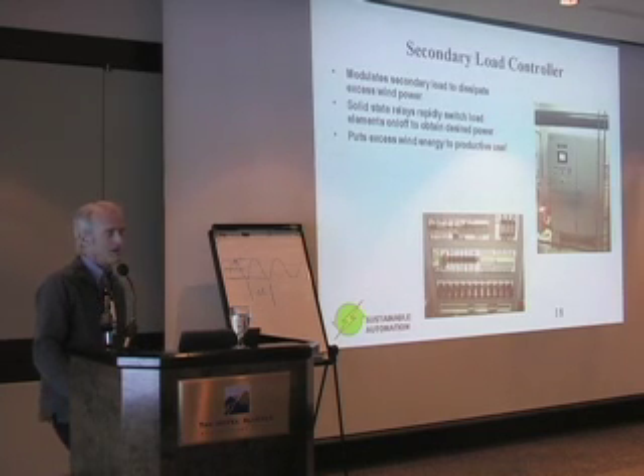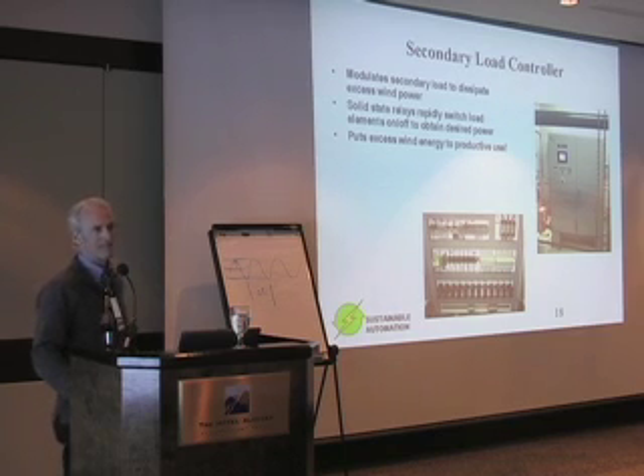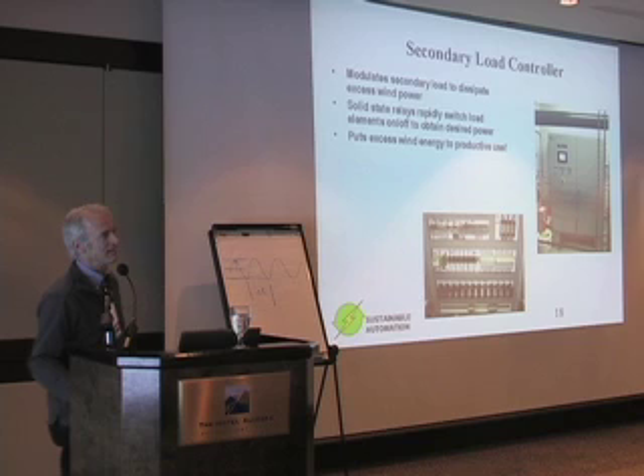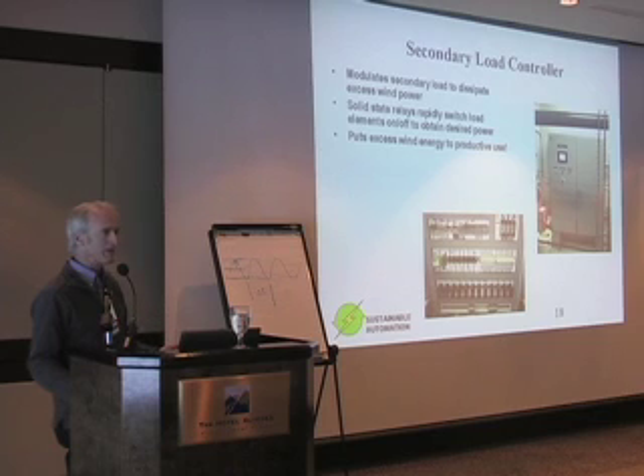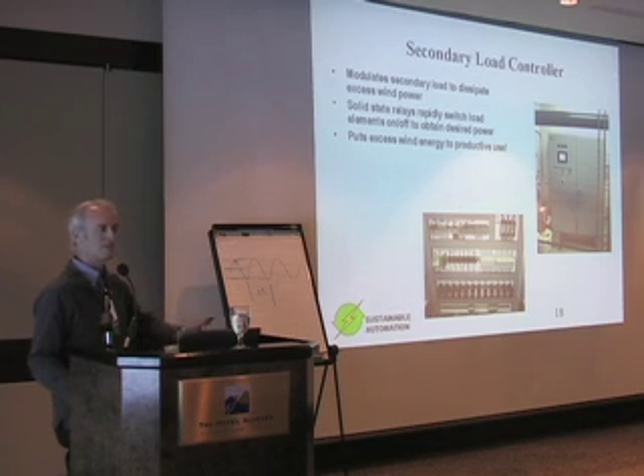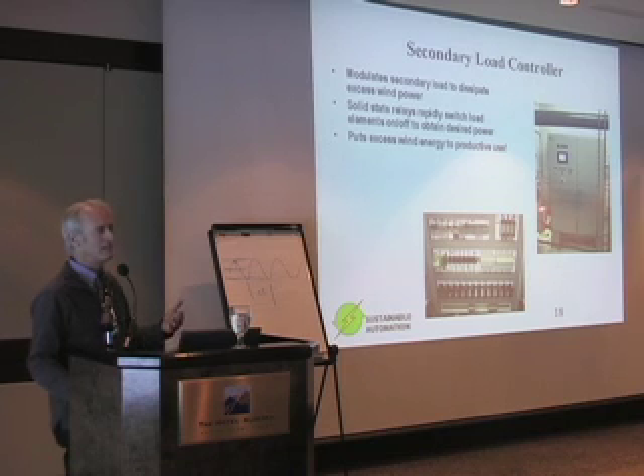So what else can we do to solve the problem? Okay, one of the simpler devices is the secondary load controller. That's a generic term that can take many forms. There are many different types of secondary loads. Resistive heating in an electric boiler, water pumping, anything. A secondary load is a load that the system has control over as opposed to the primary load, which is the consumer load that you're trying to meet. So a secondary load can be resistive heating, it can be pumping, it can be ice making, water desalination.